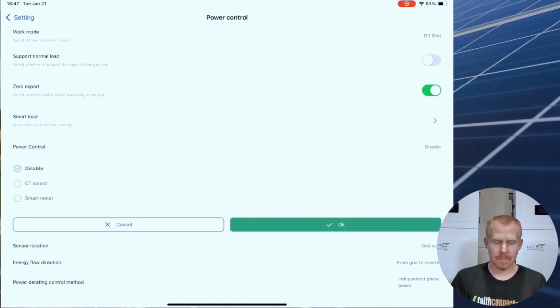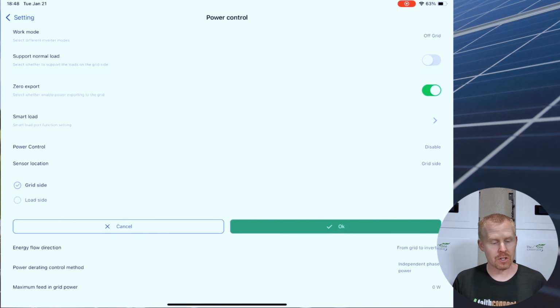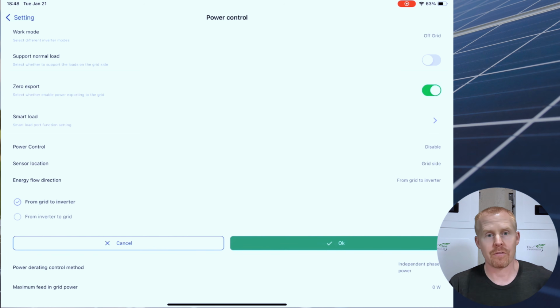Going down to power controls. So if you're in an off grid state, your power control is going to be disabled. It's not needed. If you're in a self consumption mode or in a sellback mode, you'll want to use the CT sensors. I believe the smart meter option is only needed when you have a three-phase system, and that can help track all of your power flow from those multiple inverters. Sensor location, grid side or load side. So that's going to be your CTs or your meter from your power control. I think most folks are going to end up using it as a grid side, and that's what the default value is.